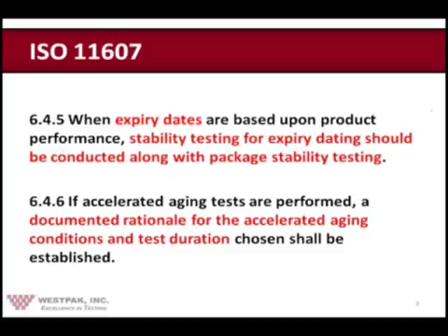because there's going to be components of your product that on some occasions can withstand 60 degrees C, for example, and we have seen other components that simply can't do that. Most package system components can because they're designed for that, but there are some product components that just can't handle that higher temperature.